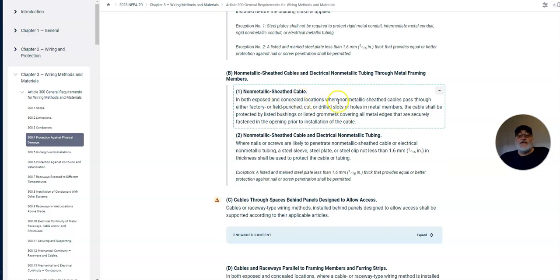In both exposed and concealed locations where non-metallic sheath cables pass through either factory or field punched, cut, or drilled slots or holes in metal members, the cable shall be protected by listed bushings or listed grommets covering all the metal edges that securely fasten in the opening prior to the installation of the cable. We're talking about non-metallic sheath tubing or non-metallic sheath cable.